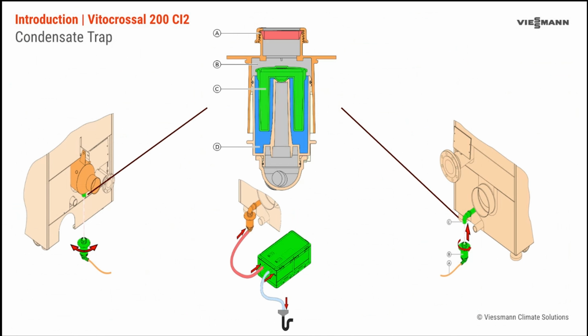Deeper look at that condensate trap. So we'll find this installed on the rear of the boiler near the flue pipe. We have a cutaway of it here. Unlike other traps that are actually trapped by condensate or water, this is a float style trap. So while it's always a good procedure to prime the trap before firing the boiler in the commissioning process, it's not actually necessary, as this will be trapped and then condensate will essentially float the overflow. And key point here, we always want to ensure that we have an air gap on our condensate pathway. This prevents vapor lock and potential backing up of condensate into the combustion chamber.